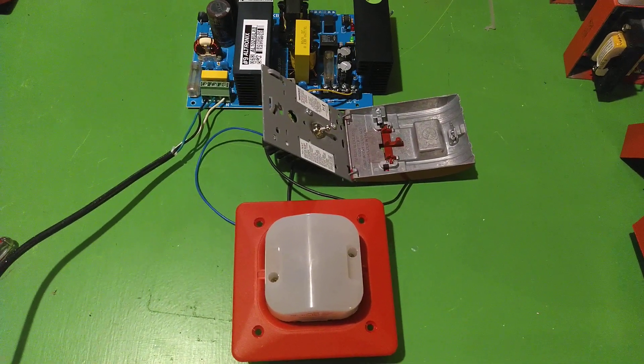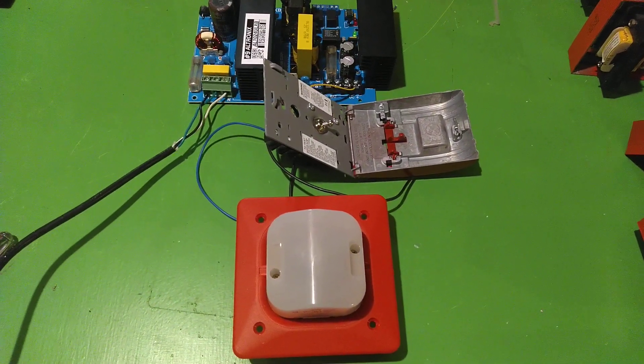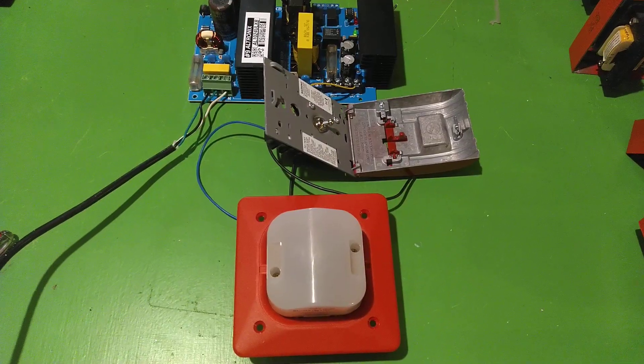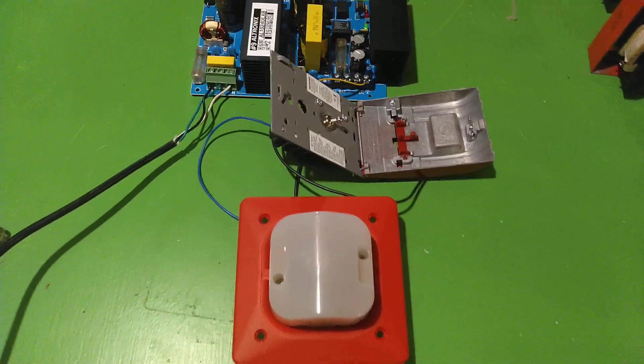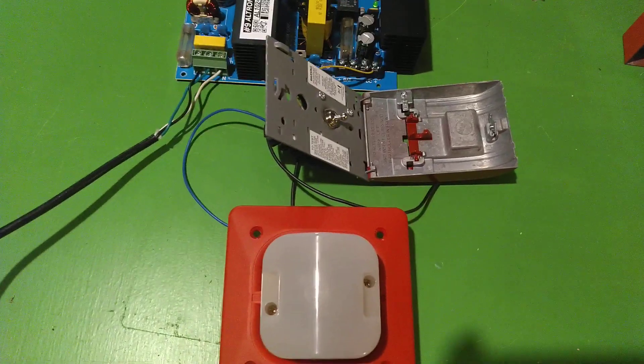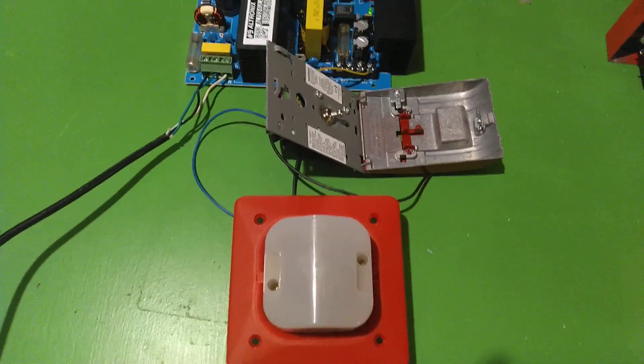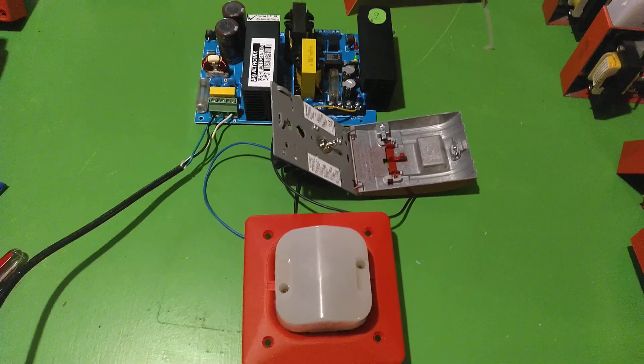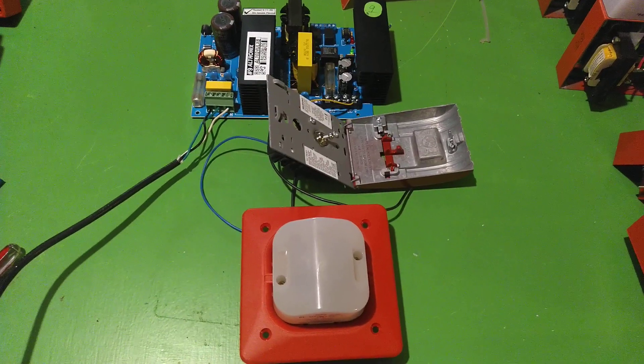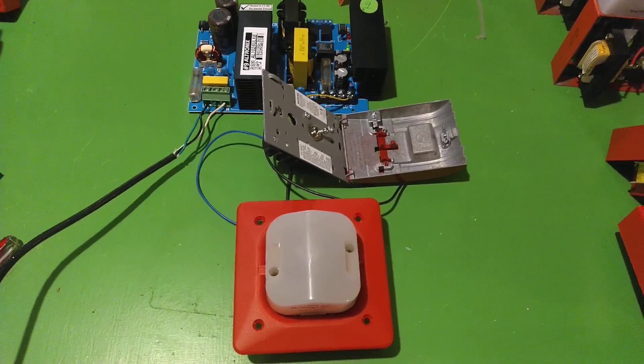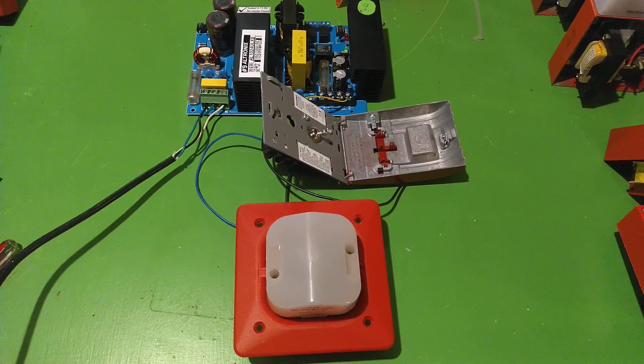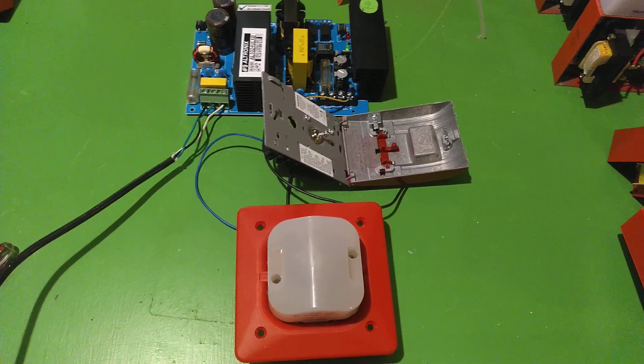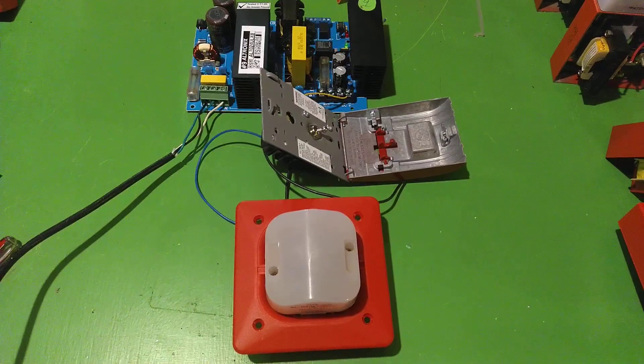The power supply is an Altronix AL1024ULXB. It's a 10 amp, 24 volt power supply rated for 8 amps when it's being used for fire.